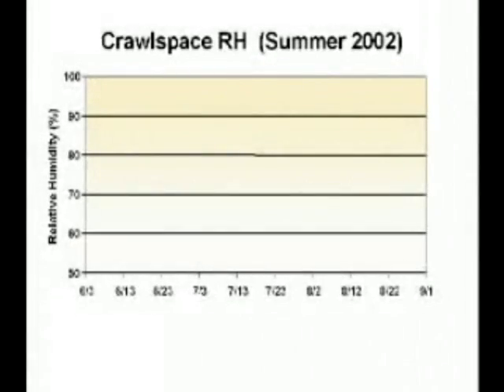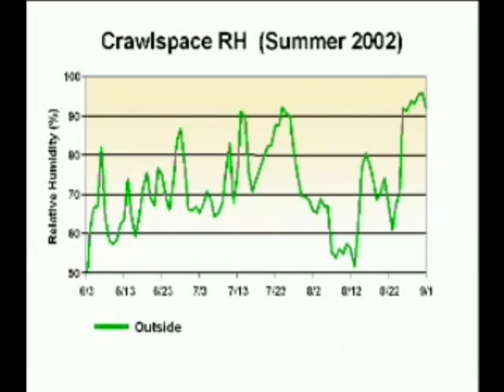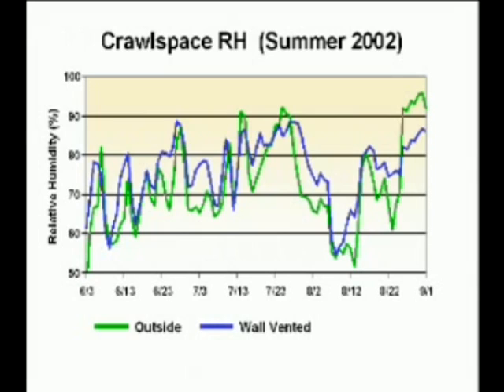We can use this graph to compare relative humidity conditions for the summer of 2002. The first line drawn on the graph is the outdoor conditions. Since this test site is in the hot and humid climate area of eastern North Carolina, it's not at all surprising to see that outdoor humidity levels stayed high most of the summer. Now let's display what happened in the control group of wall-vented crawlspaces. Notice how closely the crawlspace moisture levels follow the outdoor conditions. These crawlspaces stayed damp, with relative humidity levels above 70% most of the humid summer.